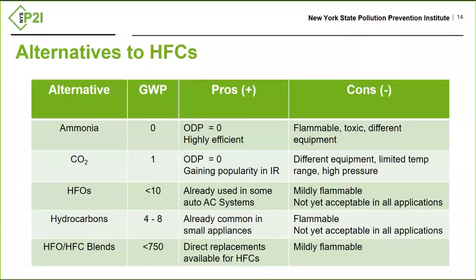HFOs, or hydrofluoroolefins, have very low GWP and zero ODP, and they're already used in some automotive air conditioning systems. They are mildly flammable, so they're not yet acceptable in indoor applications in many areas. However, they are gaining popularity.